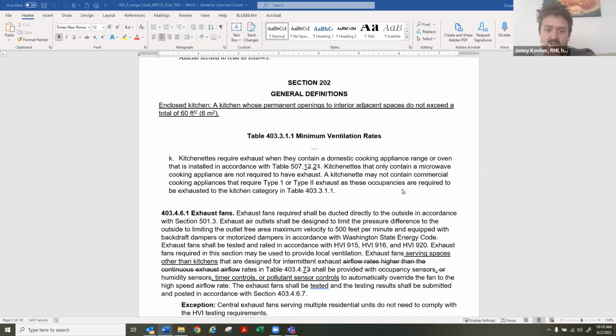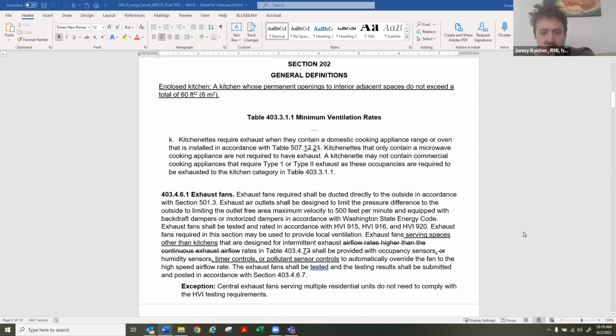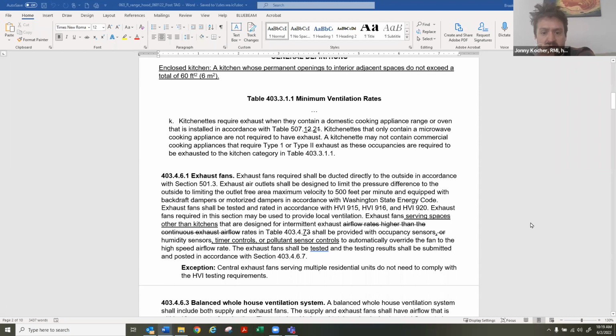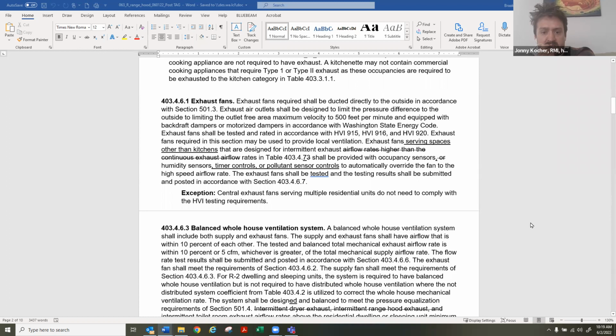So I added a definition for enclosed kitchens based off of ASHRAE 62.2. This is mostly because of a change that we made to the table that requires kitchen ventilation for enclosed versus non-enclosed kitchens. This aligns closer with what California is doing. I made a small editorial change to minimum ventilation rates, note K, because the wrong table was being pointed to. That table, I'm pretty sure, didn't exist in the code, so I pointed to the correct table. For 403.4.6.1, we made it a little more clear that this is specific for spaces other than kitchens, and added in a few extra control sensor options.